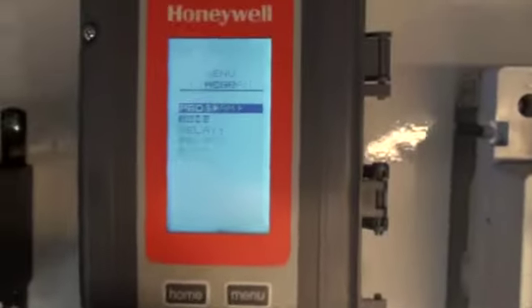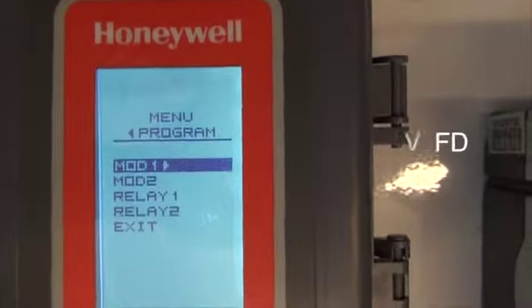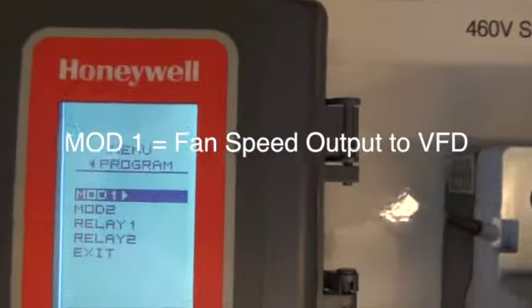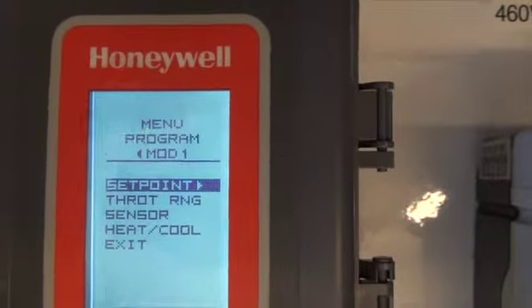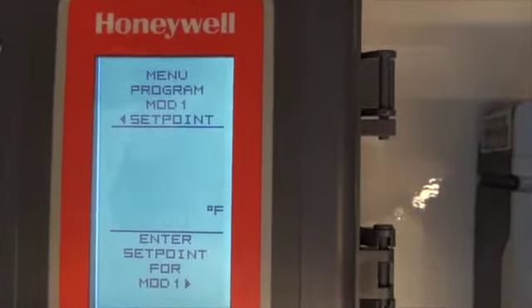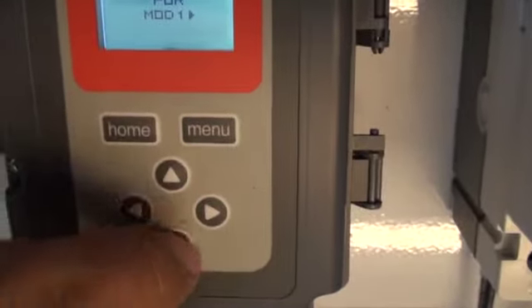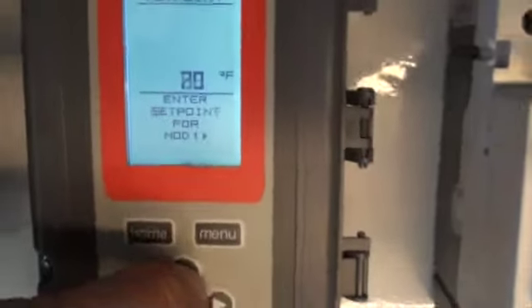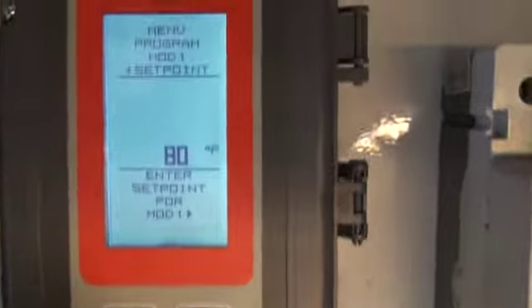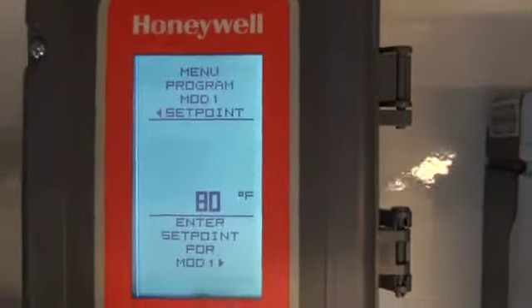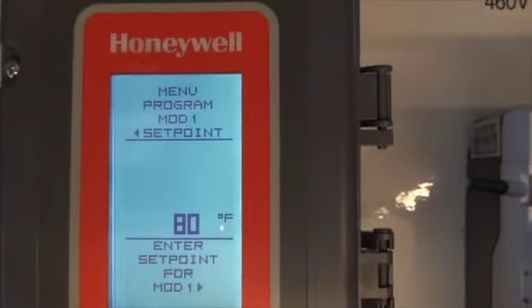You press the menu key once, goes to this, and then you press the right arrow key 1 time. And it goes right into the modulation 1. That's the output to the drive. We press the right arrow key again. The set point. I like to set my set point for cooling towers at 80 degrees, but you can adjust it up and down with these arrow keys. Up, whatever you want, down. But 80 is a good temperature for maintaining process water.